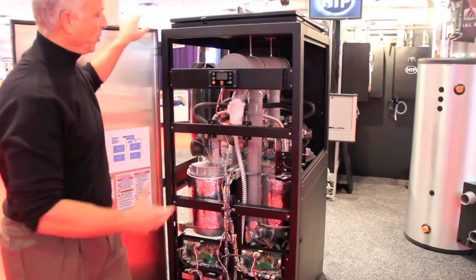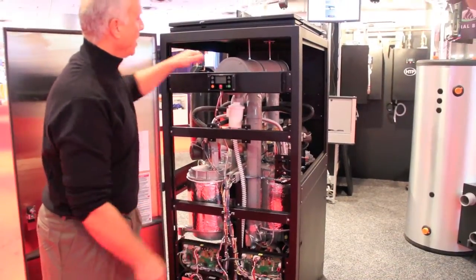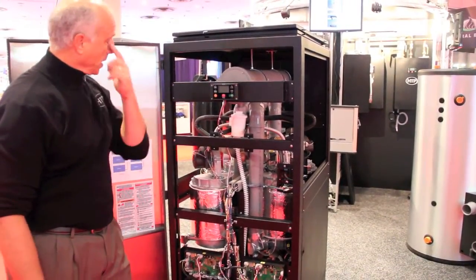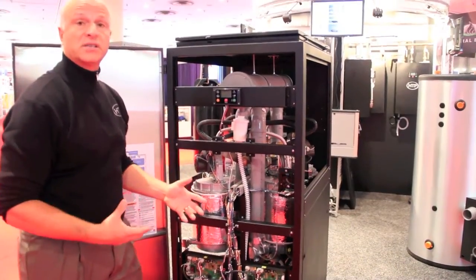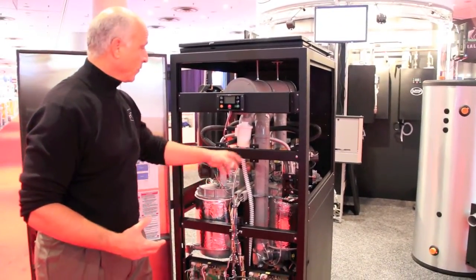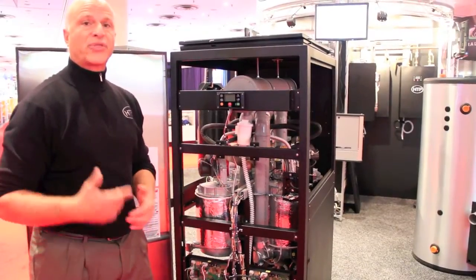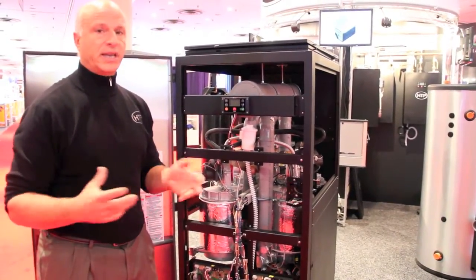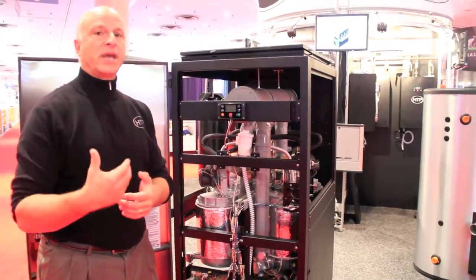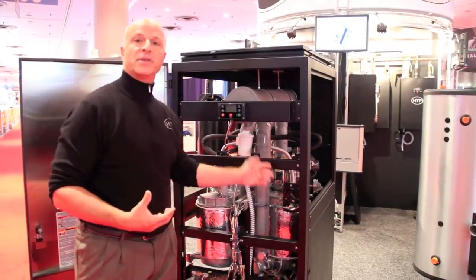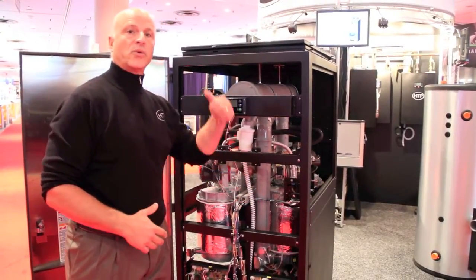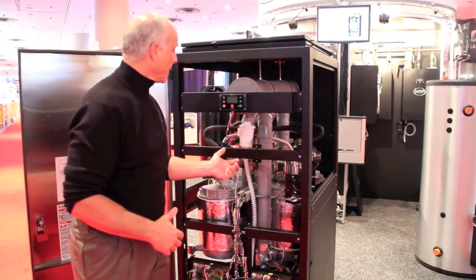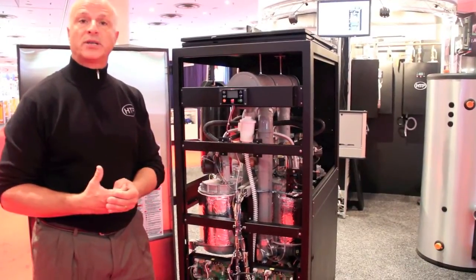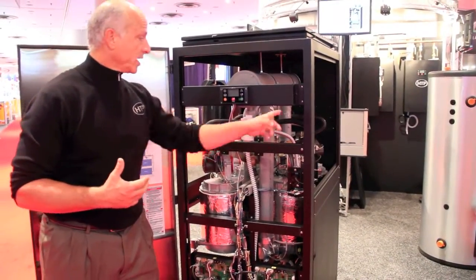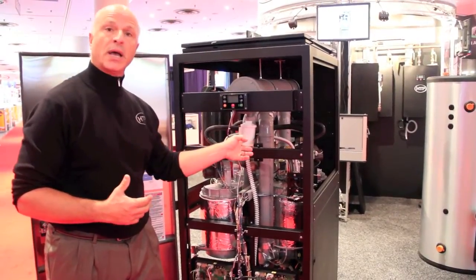All we're doing here is we're putting everything in one cabinet. We're pre-manifolding all the vents, the piping, and what this does is this gives you redundancy. So by having 4 of these in here, 1,000,000 BTUs, you have a 33-to-1 turn down, which is significant. Plus the customers are always guaranteed hot water because you got backup. If something goes down, one of the heat exchangers, the other ones will take over. The way they operate is very similar to what I talked about earlier. And let's just take a quick look. We'll move over and I'll show you how the manifold and how the things are put together.